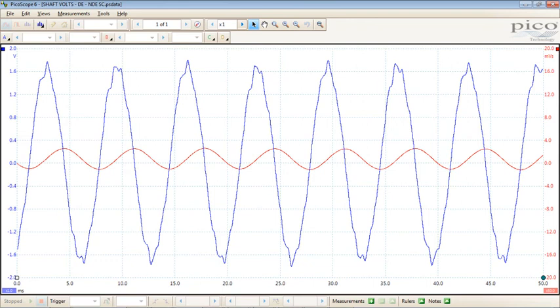I'll show you. There's a frequency spectrum later, but you see this component. That component happens to be 150 hertz. The supply was 50 hertz. The higher frequency components here are related to your slot harmonics, so your interaction between your stator and rotor slots. And then, you can't see it, but there's a 50 hertz modulation. Okay, so this is effectively with the shaft allowed to float.